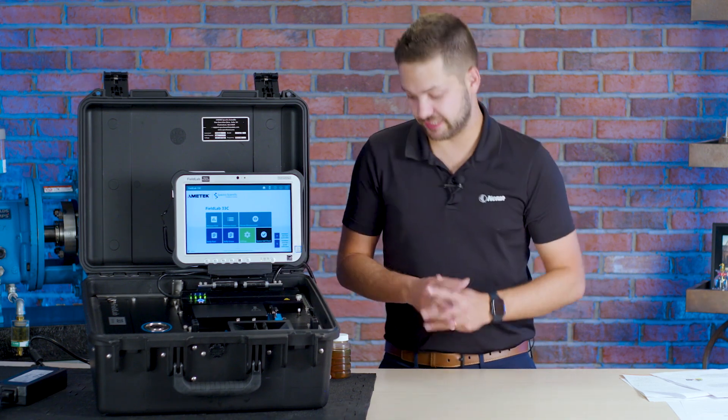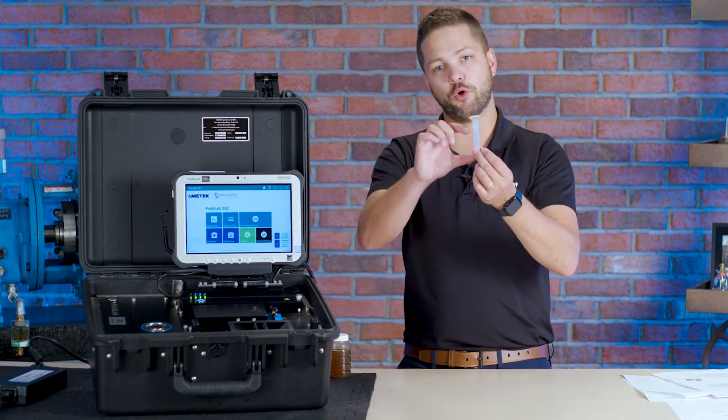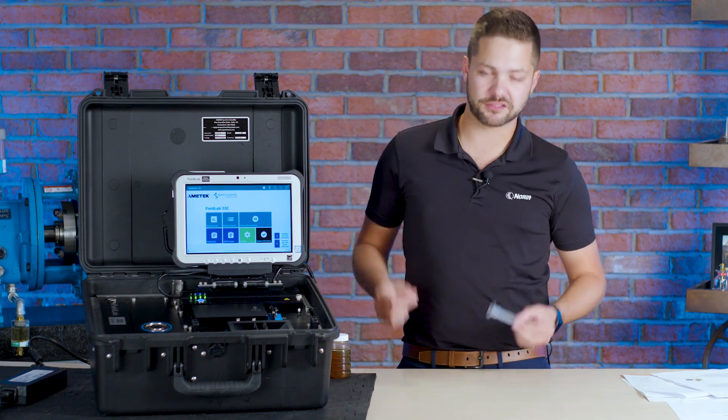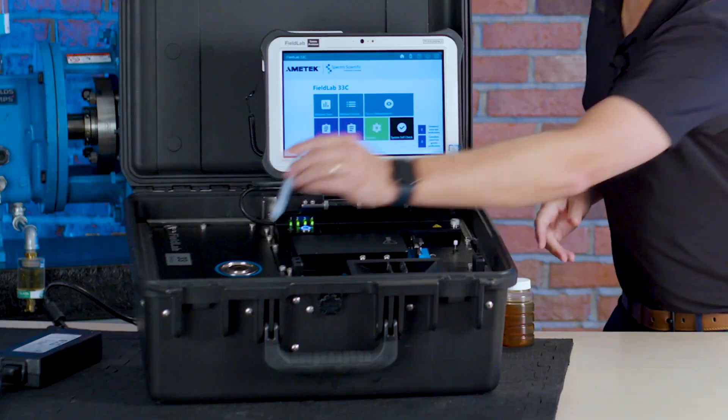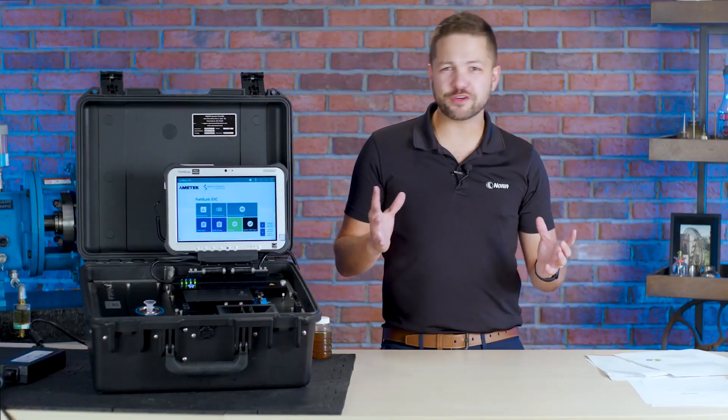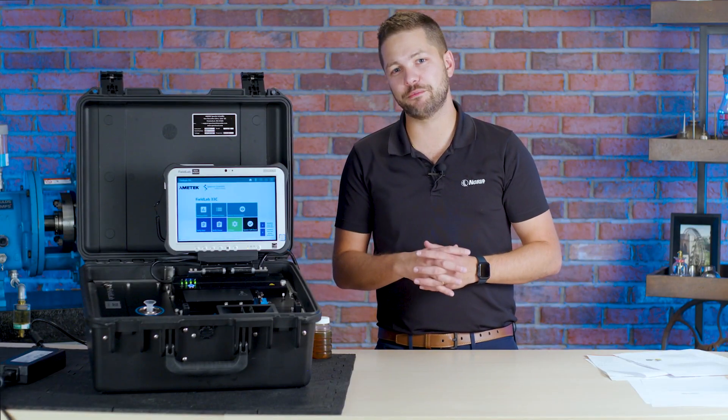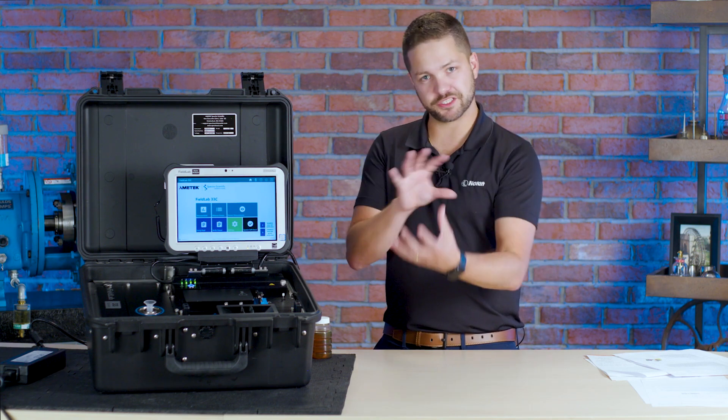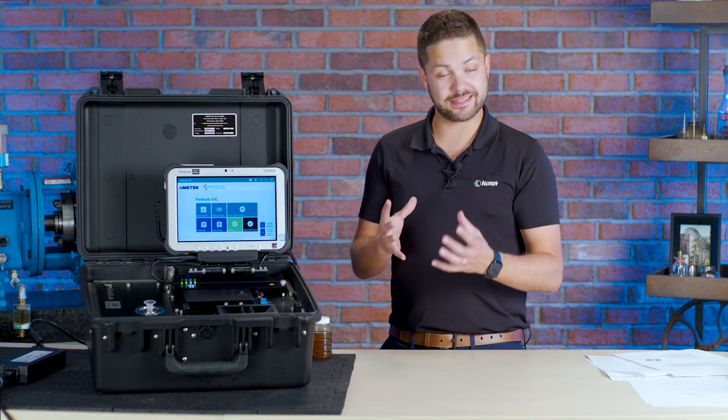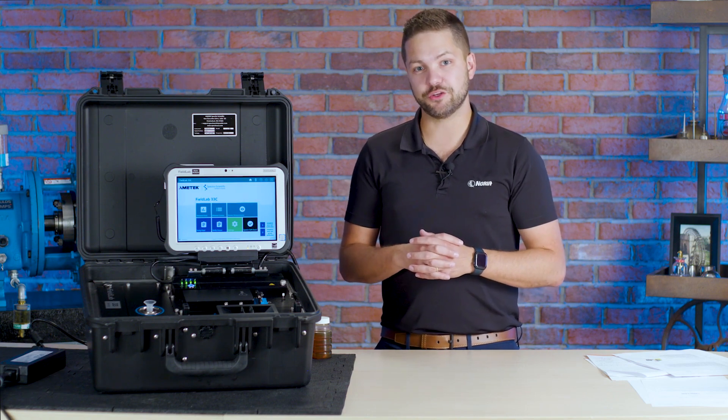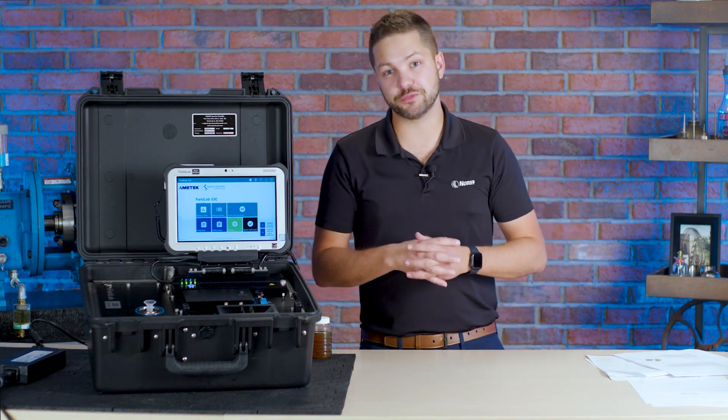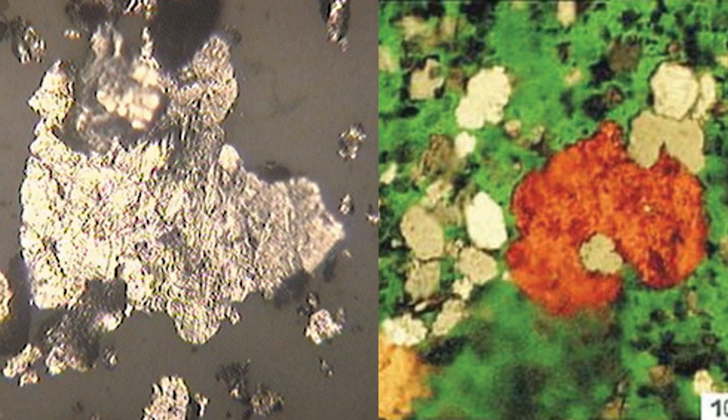The FerroCheck for example uses this little device right here. You put some oil in it or you can use a little scooper device to add some grease and all you do is you put it inside this hole right there and about 30 seconds later you'll know exactly how much ferromagnetic material is in there because it uses magnetism to indicate that content. That relates to the iron content in your oil sample. Iron debris is usually the most common element that's produced from wear.